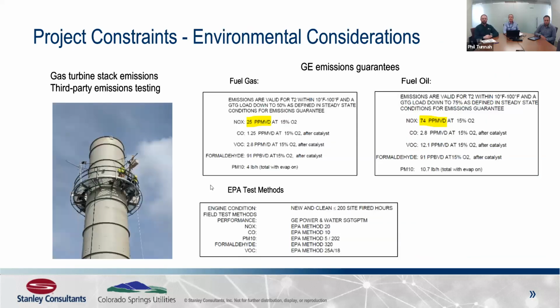In terms of emissions guarantees and the environmental aspects of combustion for these units, here are the GE guarantees involved for the project. For fuel gas, with the DLE combustors, they achieved a 25 ppm guarantee, compensated for 15% O2. For fuel oil, it was 74 ppm, also compensated.